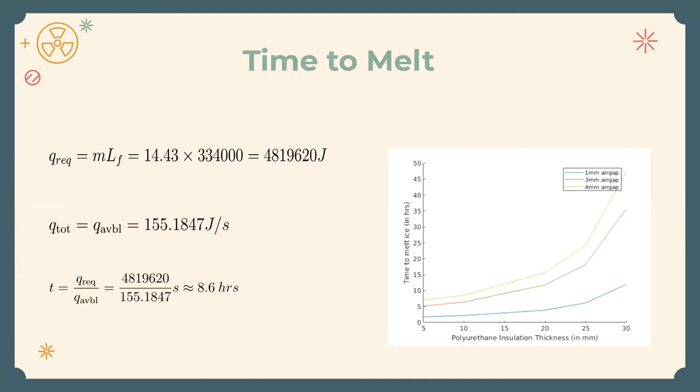Then recognizing the fact that 14.43 kg of ice was formed and the value of the latent heat of fusion, we calculate the total time required for ice to melt, which is about 8.6 hours. The graph that is plotted here gives the time to melt for various values of polyurethane thickness and air gap.